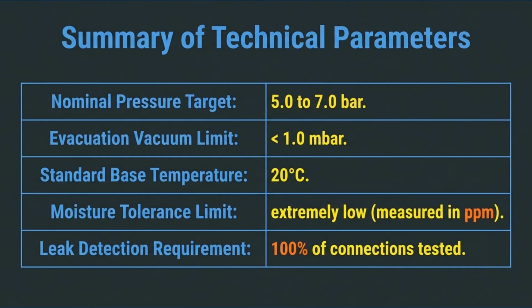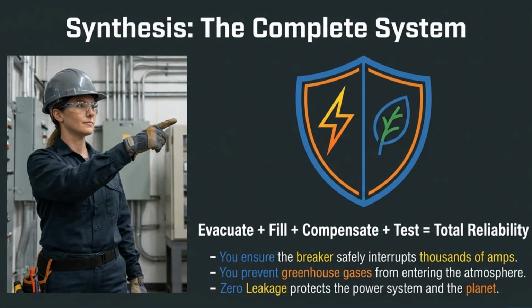Key technical parameters include a nominal pressure target of 5.0 to 7.0 bars, an evacuation vacuum limit under 1.0 millibars, and a standard base temperature of 20 degrees Celsius. Moisture tolerance is extremely low. The complete system, evacuate plus fill plus compensate plus test, ensures total reliability. This process ensures the breaker safely interrupts thousands of amps, prevents gas leakage, and protects the power grid and environment.